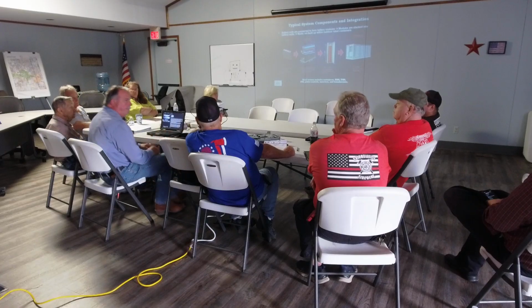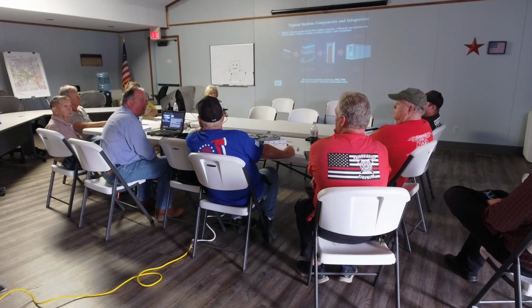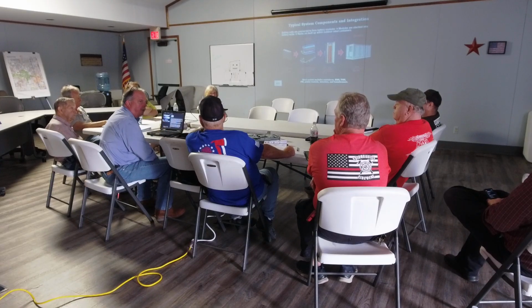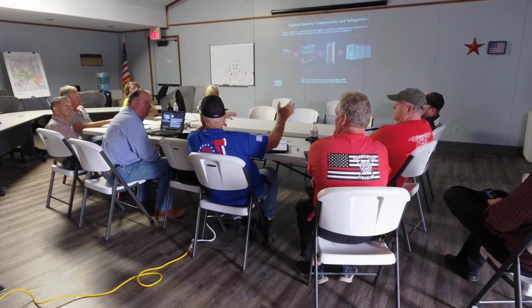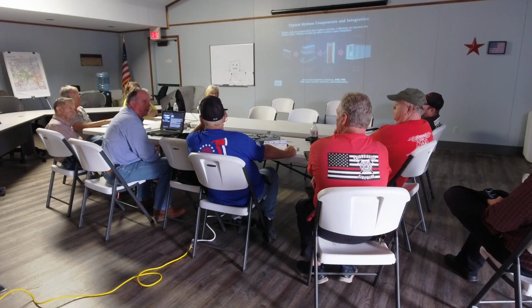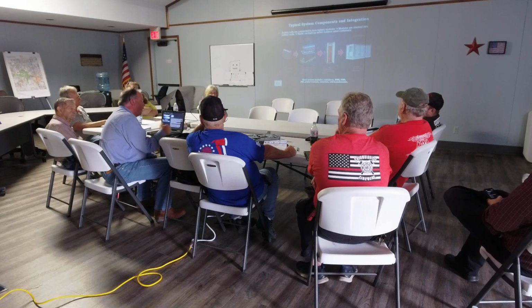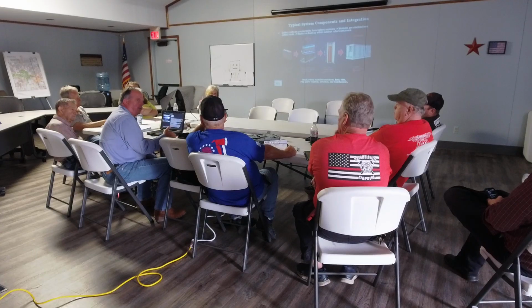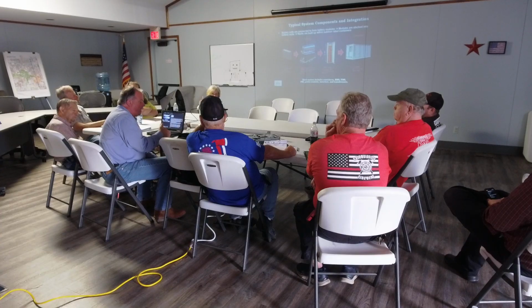Now, the stuff on the ventilator, so the gases, are any of them toxic? Is that an issue? It's not an issue as long as the setbacks are done appropriately within the site. I mean, if you get a massive amount and you get wind blowing, it's going to carry. It will, but it's also mixing and dissipating at the same time. And Fire Risk Alliance, which is a world-renowned fire safety engineering company, actually studied 35 BESS fires where sampling was done of air, soil, and water almost from the onset, and Moss Landing was one of them. They didn't find any actionable levels outside of the fence line. It was already dissipating that quickly.